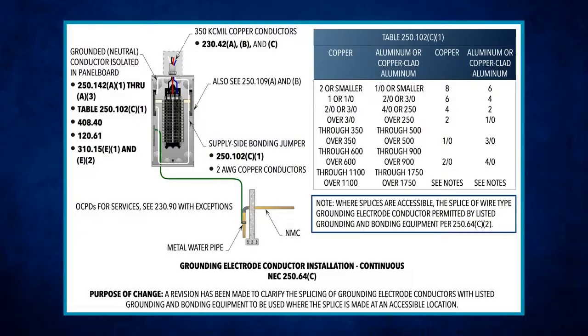True. Number 2 is what I'm saying. Yeah, because if you're looking at that, now you may have a little bit of a problem going to that. Or let's even take it a step further. Let's just say I go number 8 to the building steel, and then I go to the concrete encased electrode. What size would I need then? Or hell, Number 4.